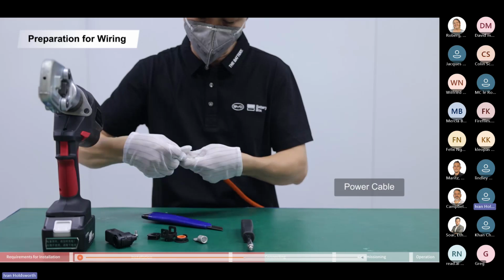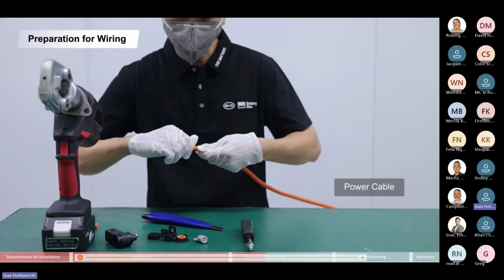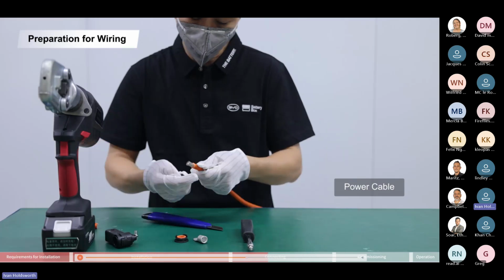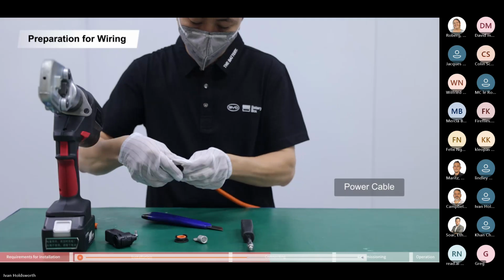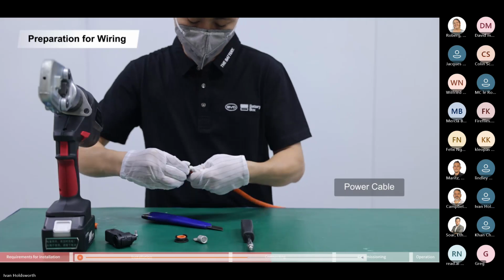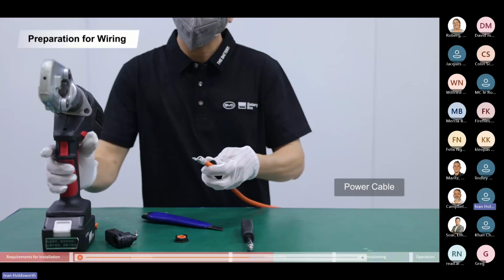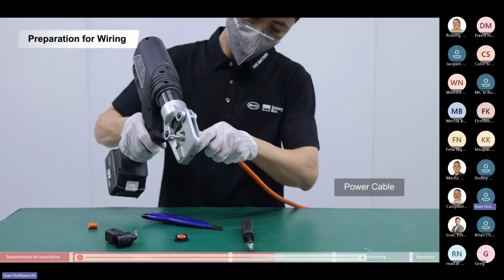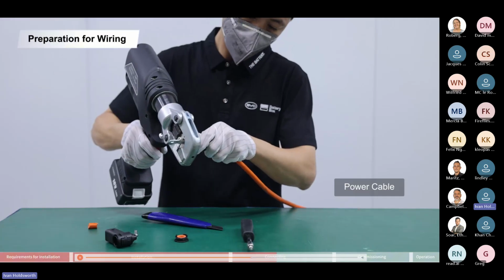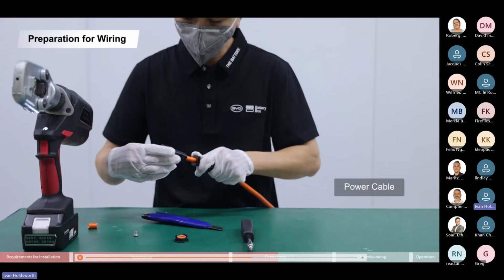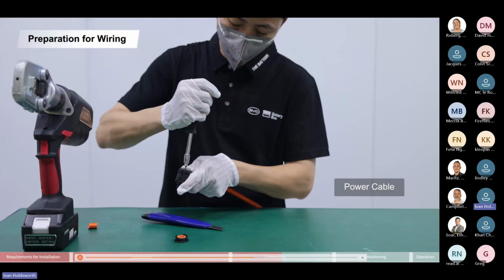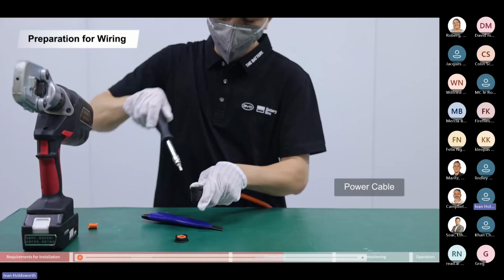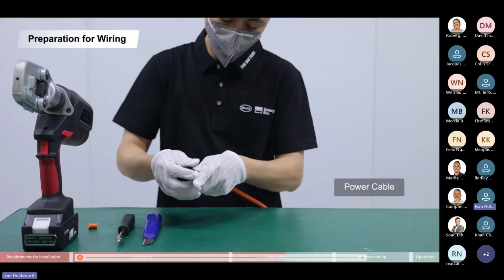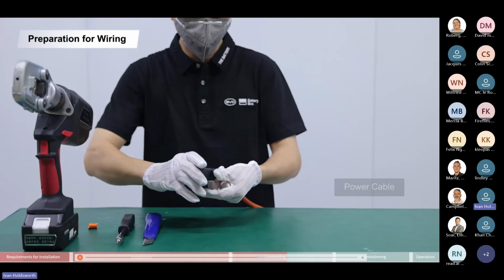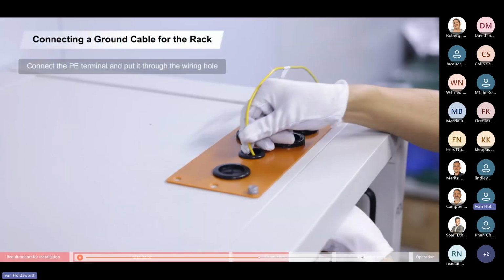This is how the power cable connects to the PDU between your inverter, your busbar, and your PDU. So what will happen is you'll attach a lug to the cable, and then that lug will get screwed to the connector. It's always best to make sure that that screw is nice and tight, because once that cap is on, it's actually quite difficult to get off. So here we can see the screw going in. We always recommend tightening down nice and tight, or if you have new installers, to use a torque wrench, just to make sure they get it at the right torque.